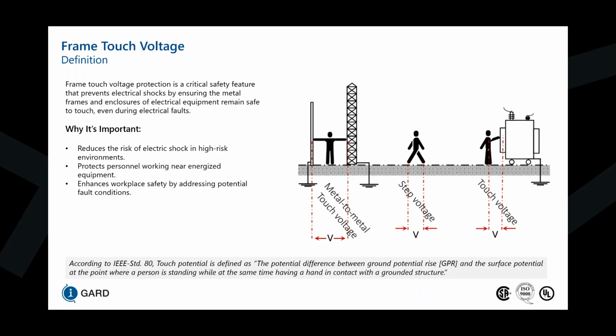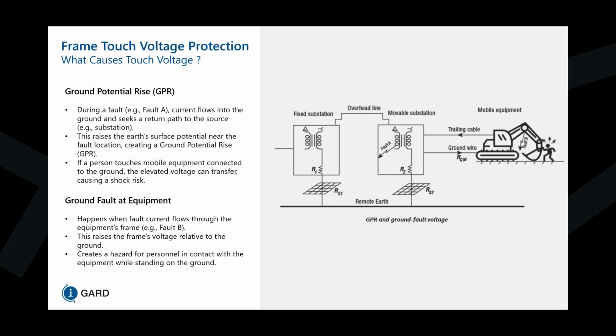So according to IEEE 80, touch potential is defined as the potential difference between ground potential rise and the surface potential at the point where a person is standing while at the same time having a hand in contact with a grounded structure. So what causes touch voltage? During a fault, let's say if we have a fault here, current flows into the ground and seeks a return path to the source, which would be the substation here. This raises the Earth's surface potential near the fault location, creating a ground potential rise. If a person touches the mobile equipment here, connected to the ground, the elevated voltage can transfer, causing a shock risk.